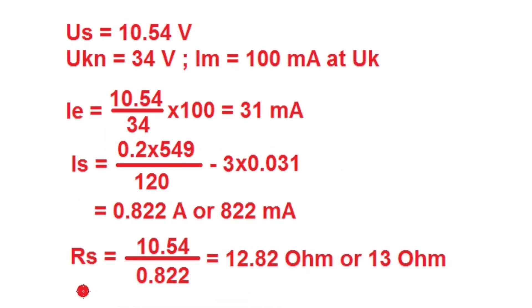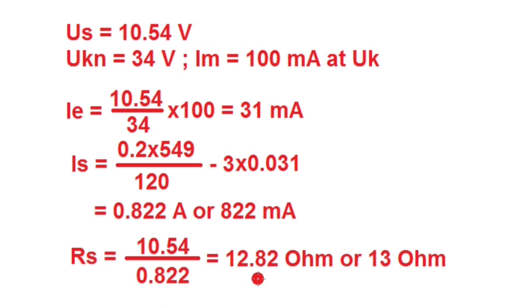Since the stabilizing voltage and relay setting current are now known, we calculate the stabilizing resistance: RS = Us / Is = 10.54 / 0.822 = 12.82 Ω. A 13 Ω stabilizing resistance can be connected in series with the residual coil of the motor earth fault protection.